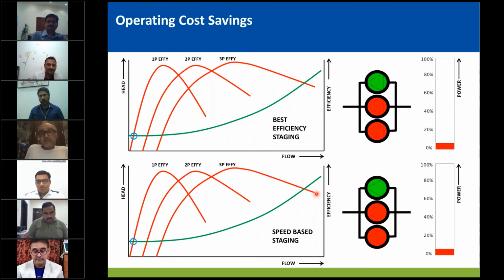Now let's look at what happens when the first pump starts in both cases. So the first pump starts. In both cases, up to this point, there is no change. Both are the same. But when it reaches this point, the best efficiency staging knows that it's dropping in efficiency scale. This is the efficiency scale, and if you load the pump further, you're dropping in efficiency scale. And that is going to consume more power, versus in the best efficiency, you have the opportunity to stage the second pump and operate 2 pumps at low speed.